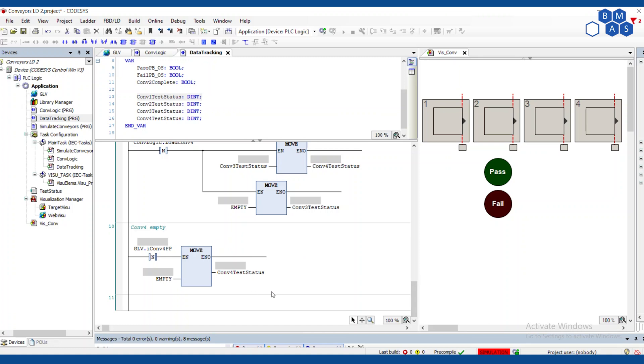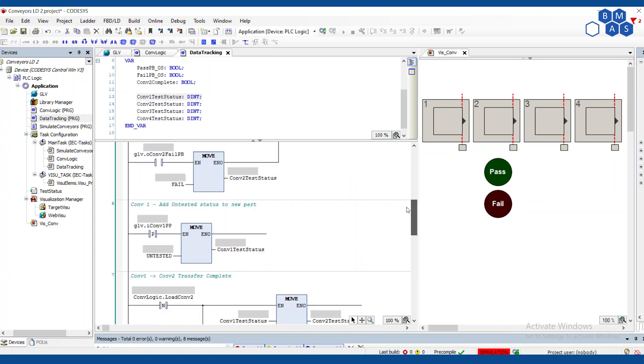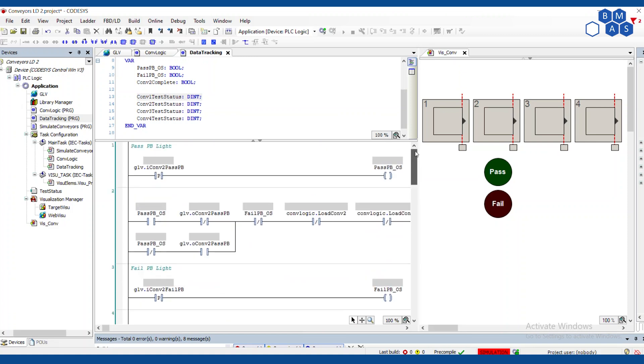And then when conveyor four goes empty, again, this is the oddball because it's the end. When we see that there's nothing there anymore, nothing at that part present sensor falling edge, then we're just going to move empty into conveyor four test status. And for this simulation, I'm imagining that an operator puts a part into conveyor one and takes it off of conveyor four just by hand.